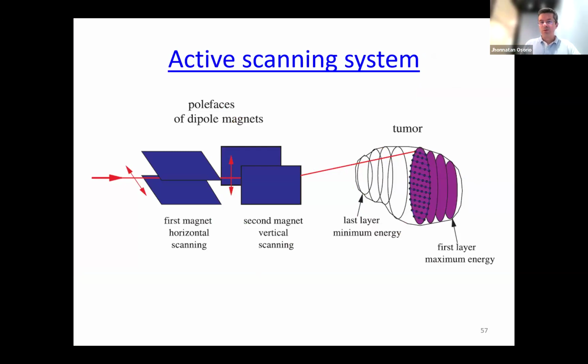The one that is most commonly used since like 10 years or more is the active scanning system, which is like the old-fashioned TV. Basically you have two different dipoles, which scan the beam vertically and horizontally, and then you can control the energy, or the depth of the beam, with your accelerator.